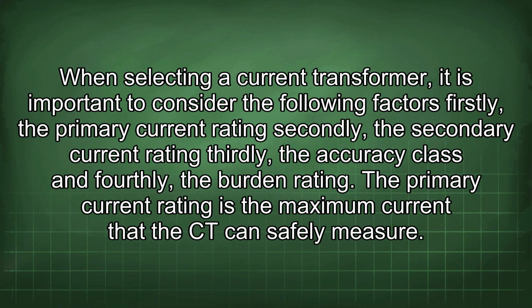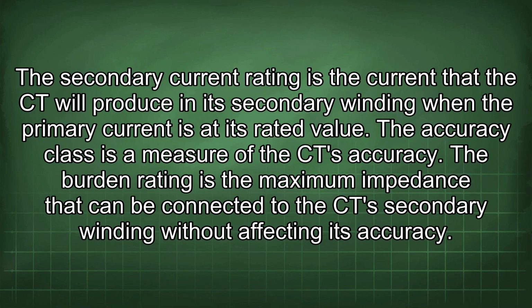When selecting a current transformer, it is important to consider the following factors. Firstly, the primary current rating. Secondly, the secondary current rating. Thirdly, the accuracy class. And fourthly, the burden rating. The primary current rating is the maximum current that the CT can safely measure. The secondary current rating is the current that the CT will produce in its secondary winding when the primary current is at its rated value. The accuracy class is a measure of the CT accuracy. The burden rating is the maximum impedance that can be connected to the CT secondary winding without affecting its accuracy.